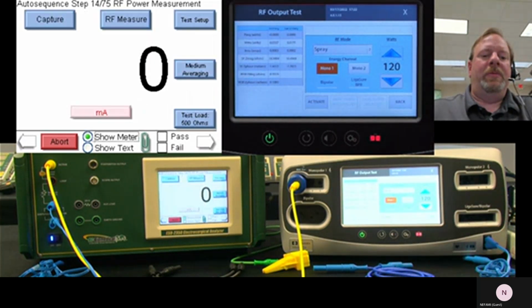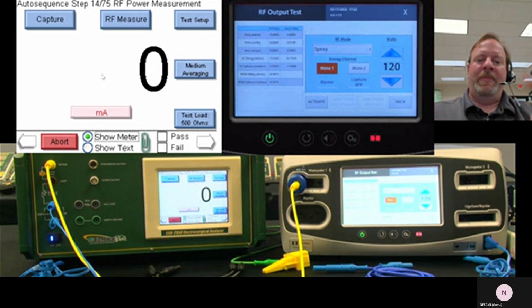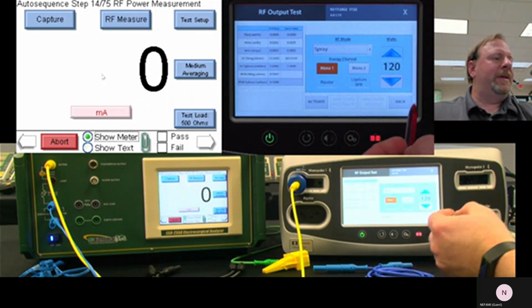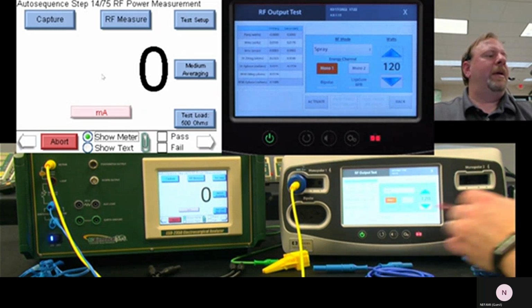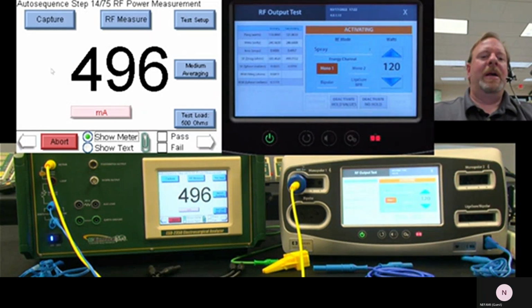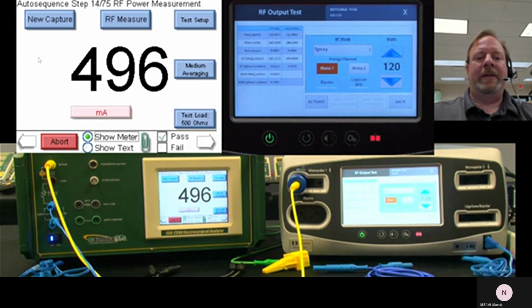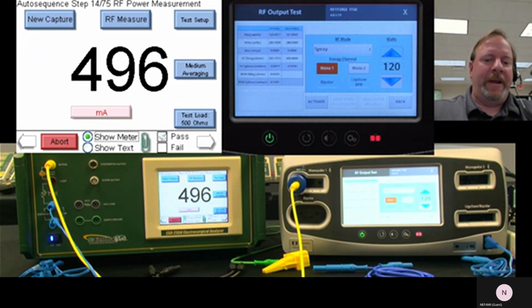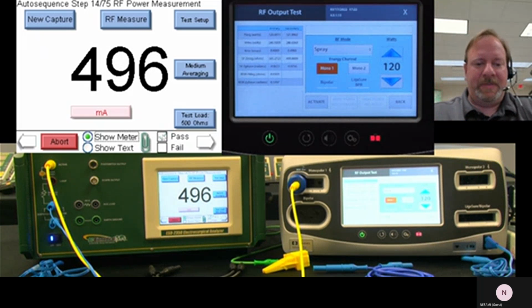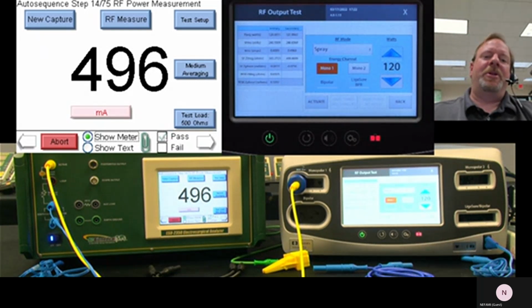First I'm going to do show meter. Now this is in measurement mode, so it's live. It's taking readings, and I hit active. I've got my reading. I hit capture and deactivate. So now it stored my reading. It analyzed it, and it said it was good. So inside this auto sequence are built the limits for the test. So it knows whether it has to be within a current range. I don't know what it is specifically for this one, but if the measured current isn't within range, it'll show you that it fails.